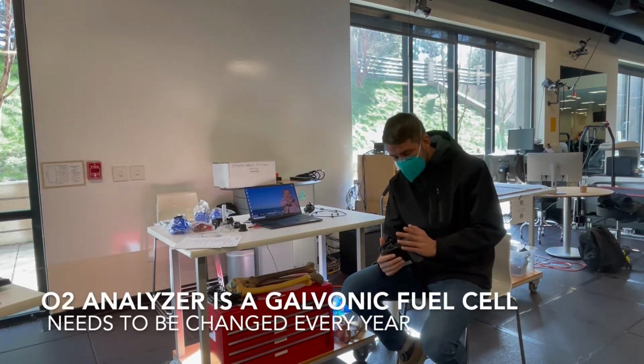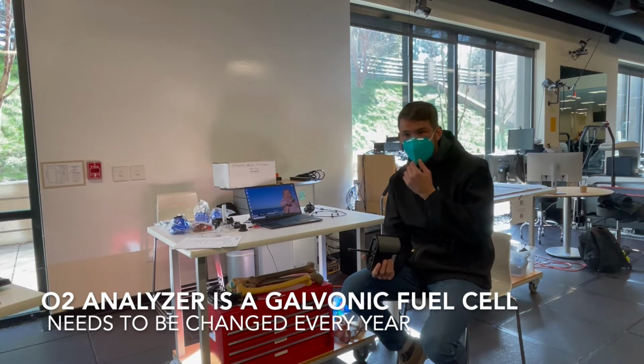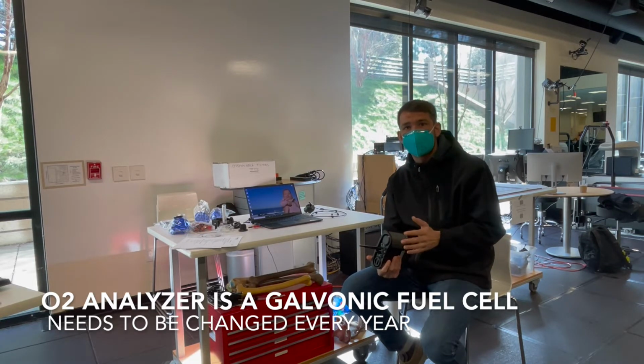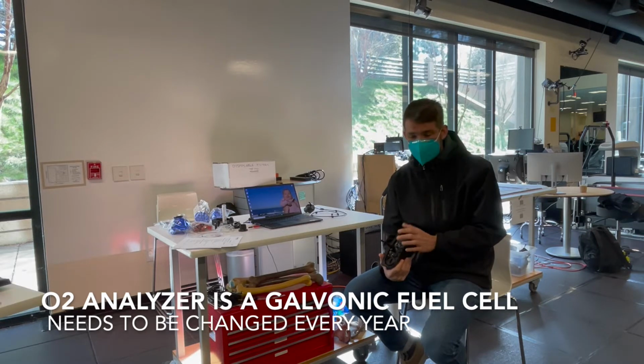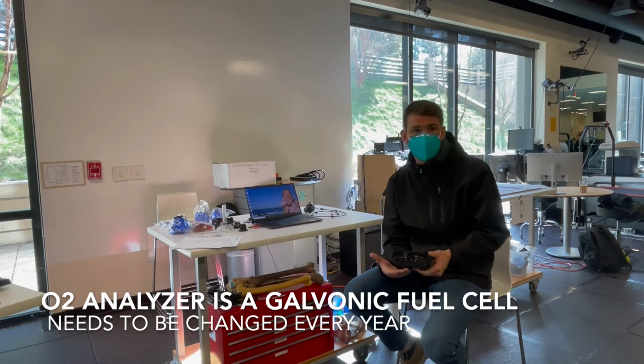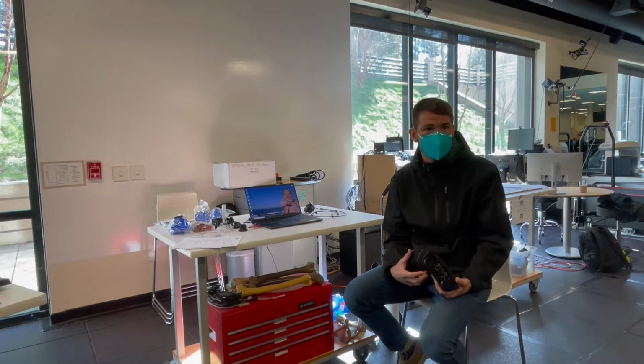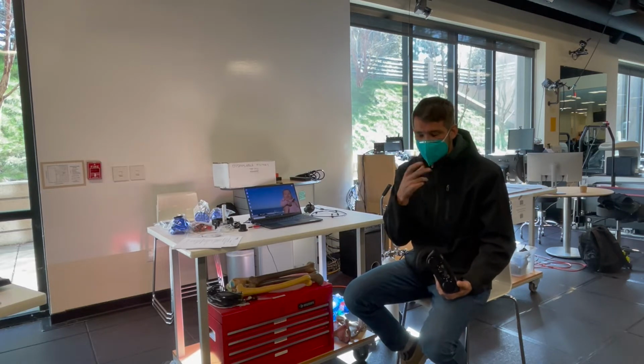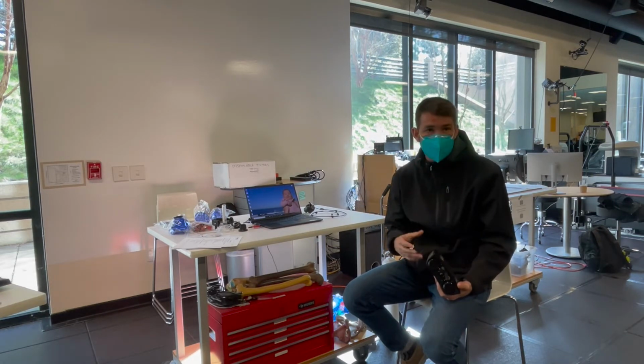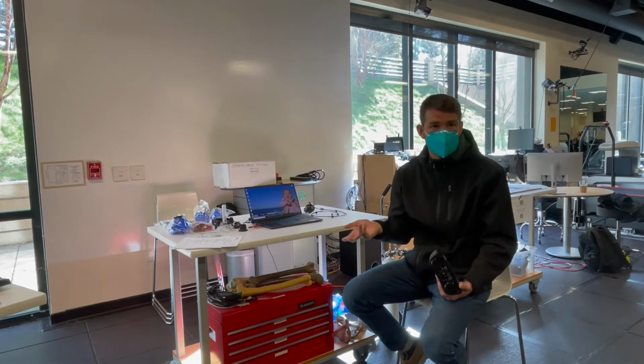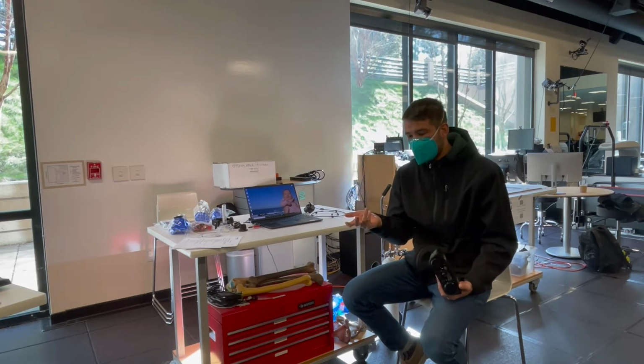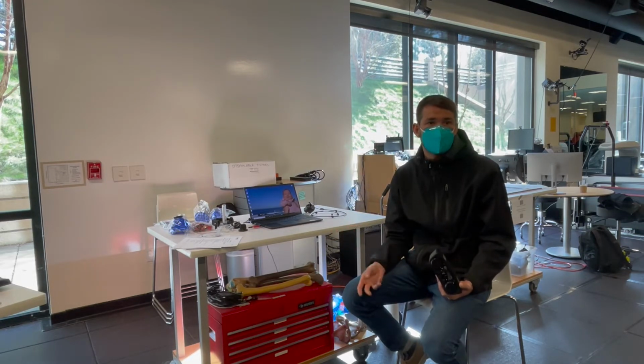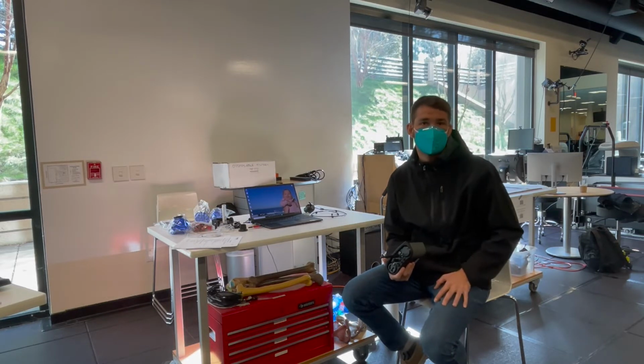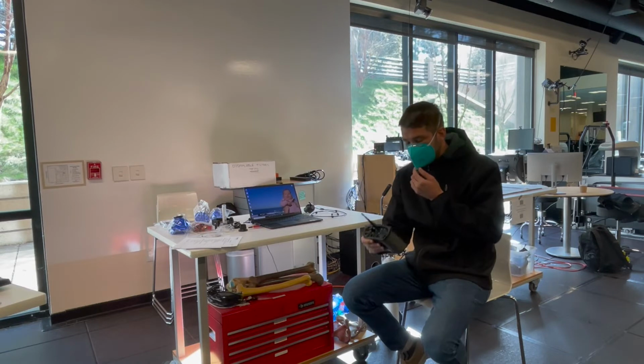And then the O2 analyzer, it's called a galvanic fuel cell, so it's based on a chemical reaction, and that's why every year it needs to be changed, because essentially that cell just becomes exhausted over time. And so what happens is the system applies what's called a gain to the measurement. So over time, it just can't apply enough of a gain to get an accurate reading on the measurement, so the cell just needs to be changed.